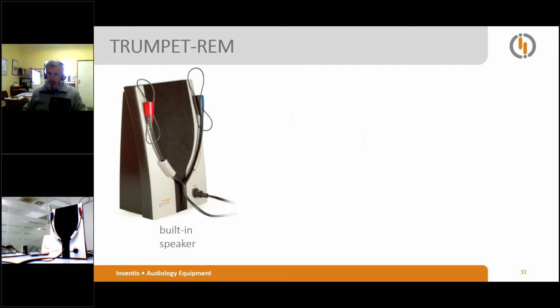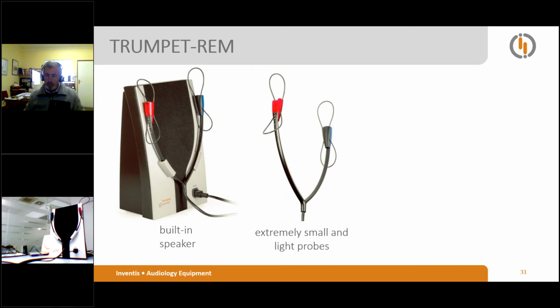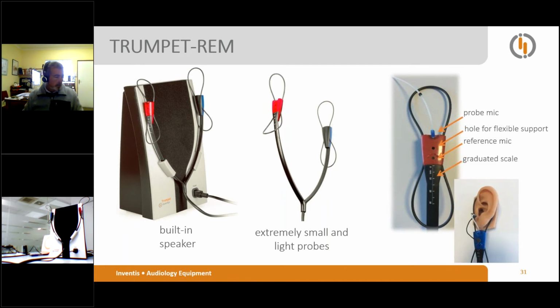So this is the Trumpet and this is its built-in speaker, relevant for performing REM tests, but using the speaker you can even perform pure tone audiometry and speech audiometry in free field. Extremely small and light probe. Each probe contains the reference microphone and the probe microphone, as shown in the pictures. The probe microphone, with the silicone tube, acquires the sound close to the eardrum. The reference microphone close to the pinna acquires the sound before the amplification provided by the ear canal and the hearing aid, if the patient under test is wearing the hearing aid.